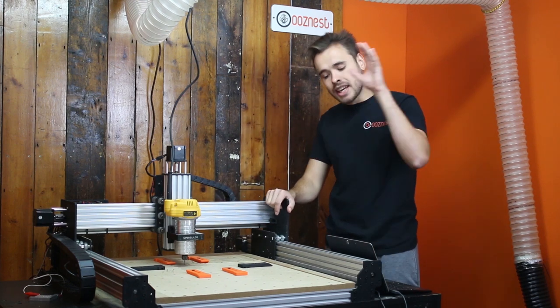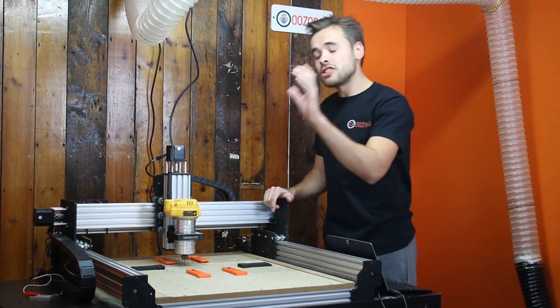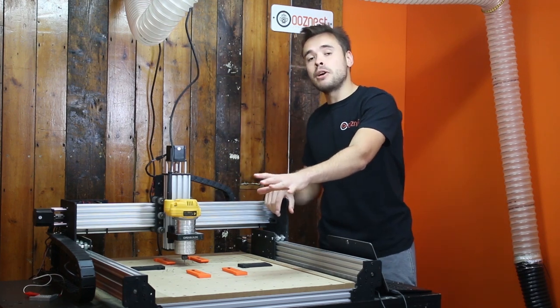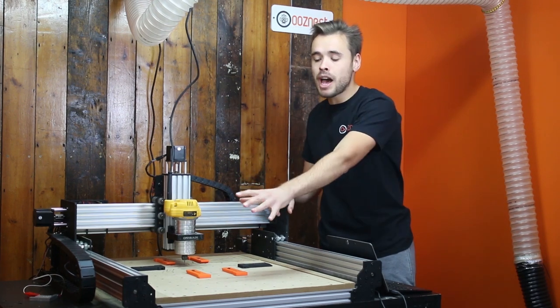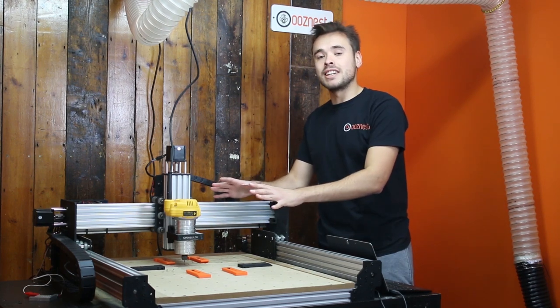This is because when we hit that button, it killed the process on the machine. So just to recap, this is the correct way to set up an emergency stop button with the machine. We want it to kill the power, but also kill the process. So when you unlock it, the machine does not carry on running.